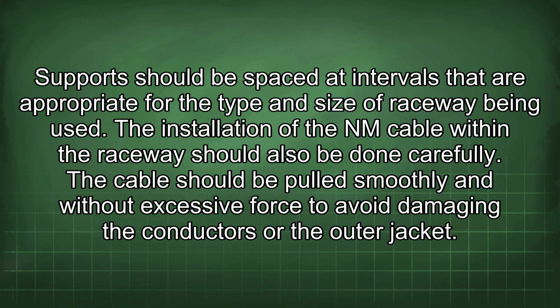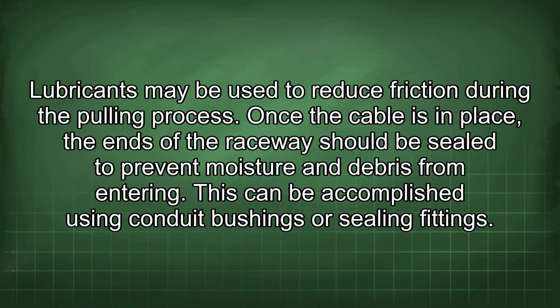The installation of the NM cable within the raceway should also be done carefully. The cable should be pulled smoothly and without excessive force to avoid damaging the conductors or the outer jacket. Lubricants may be used to reduce friction during the pulling process. Once the cable is in place, the ends of the raceway should be sealed to prevent moisture and debris from entering. This can be accomplished using conduit bushings or sealing fittings.